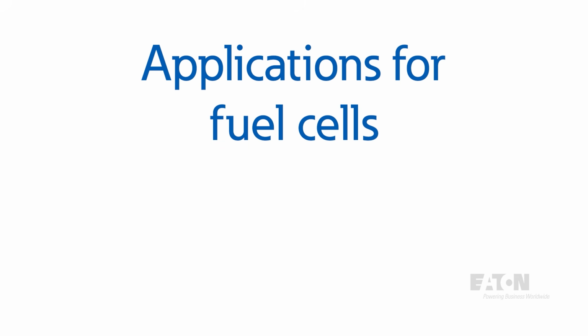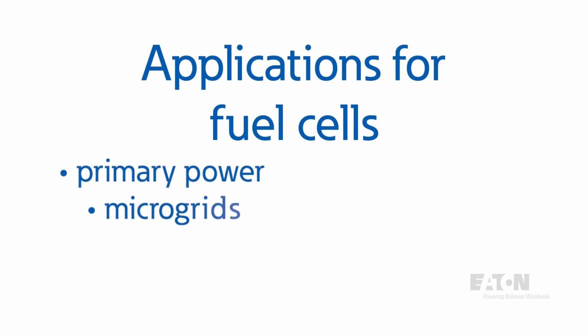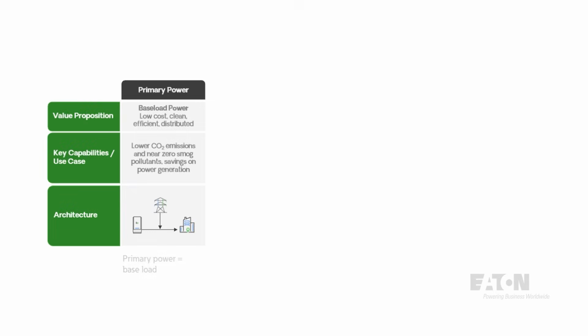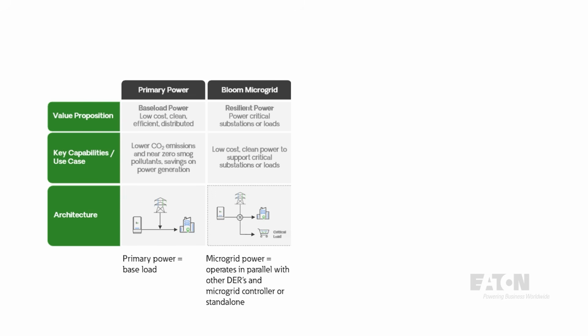So what are the scenarios where you would see a fuel cell? Applications of fuel cells vary from primary power to microgrids to off-grid power. For primary power, the unit provides a fixed level of base load power. This is primarily how we're using the Bloom unit here at the PSEG. With microgrid applications, it acts in parallel and can be used with other DERs and a microgrid controller, or as a standalone unit that separates from the grid and protects critical loads to provide resilience.